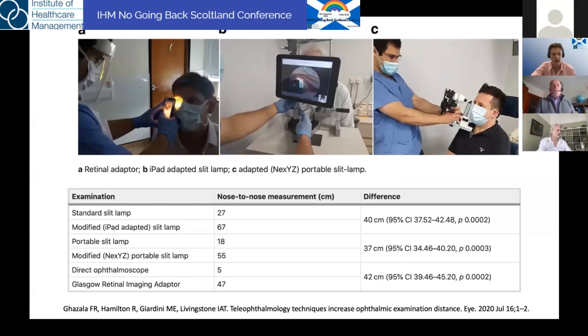And then COVID landed. We were already doing remote examinations because in itself it was useful, but suddenly there was increased pressure to increase distance from patient to doctor. By having a virtual digital viewfinder, you're suddenly increasing the distance from patient to doctor by about threefold. It's a breath guard of sorts in the form of a wipeable tablet. It also lended itself well to other work we were doing to replace the direct ophthalmoscope — where you're an inch away from the patient — with something smartphone-based that allows arm's-length examination.